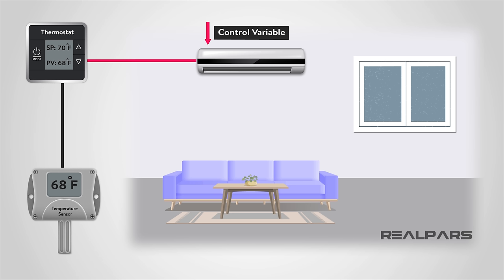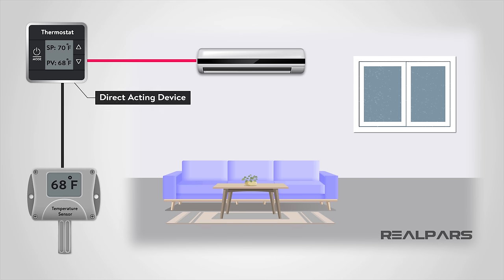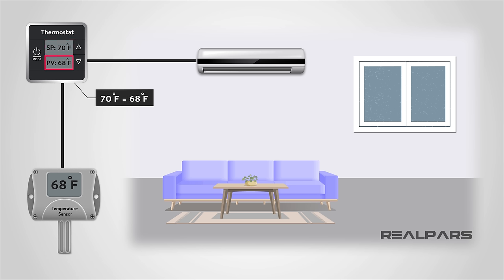The heating or cooling unit is the control variable, or CV. The control variable may also be referred to as the manipulated variable, or MV. There are different types of control action, and for the temperature control in the house, the controller action is a direct acting device, meaning that the calculations are set point minus process variable. In our house example, we have a set point of 70 and the process variable is 68. When we subtract the process variable from the set point, we see that we have a value of 2. The result is called the error, or E, in our process.